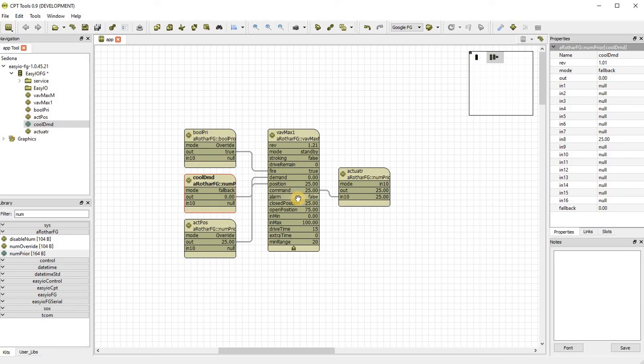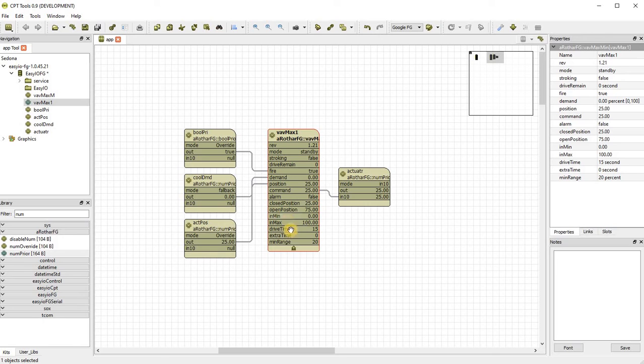Also in the block we have this alarm point. What we were trying to do was offer a self-ranging VAV control. So we can put in the actuators and we don't have to set the limits on the actuator. We can do that via software. It saves us an extra step and some labour on a job. So if it ranges open to 25 and 75, it will software limit to those ranges.